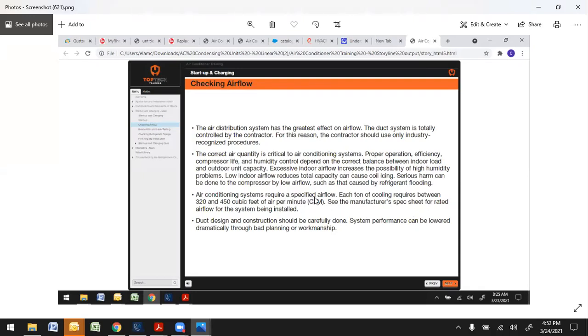Air conditioning systems require a specified airflow. Each ton of cooling requires between 320 and 450 CFM, cubic feet per minute. See the spec sheet for the rated airflow for the system being installed. They used to say 400 CFM per ton. Yes, that will work, but it may not dehumidify like the customer wants. It may not cool like they want. It may be loud. So depending on the system you're putting in, don't take it for granted that it's just 400 CFM per ton. And then you also have to factor in static pressure as well.